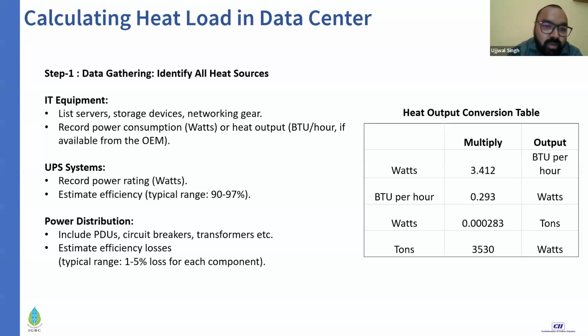Now for UPS systems, the typical efficiency range is 90 to 97%. For accurate estimation, you need to measure the input and output of your UPS. The difference between input and output is your heat generation, and it covers everything connected to the UPS, like auxiliary equipment as well.